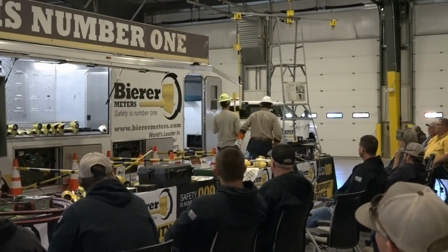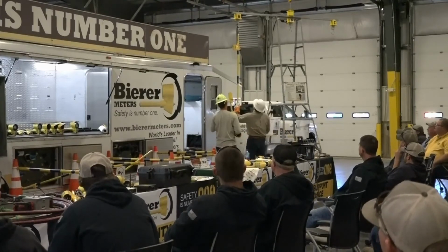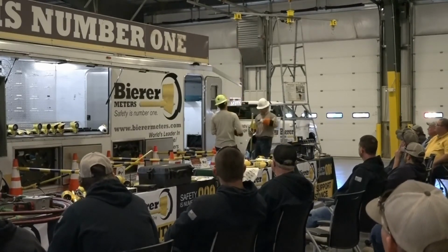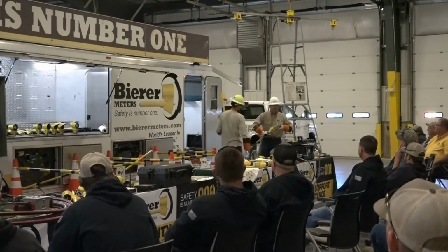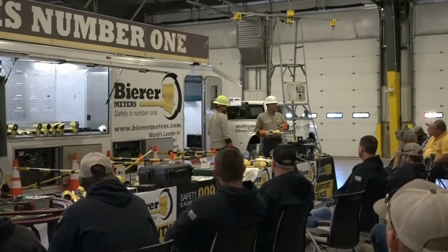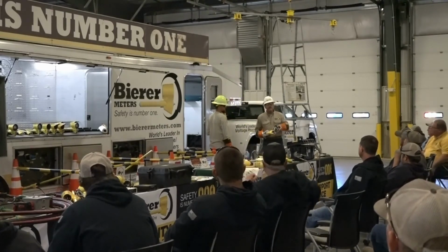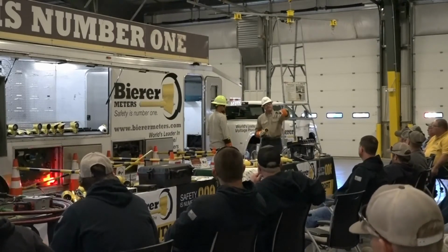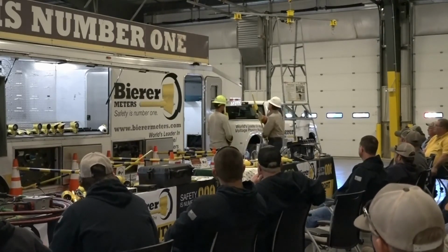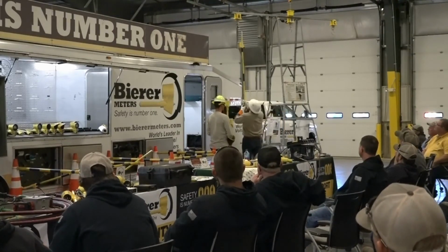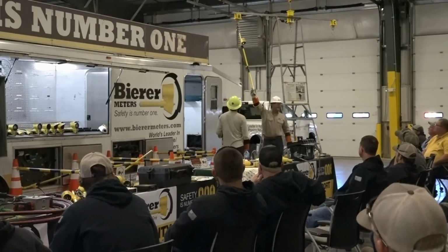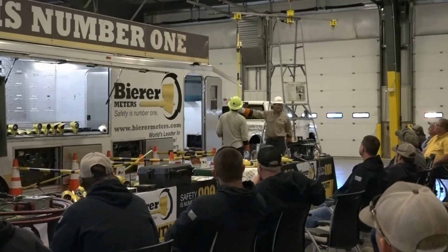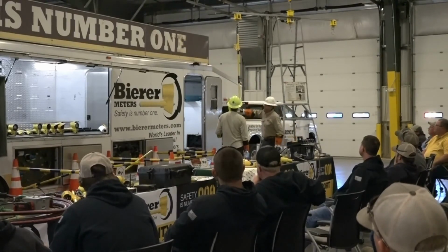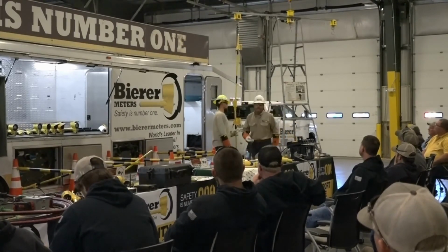You come this way. Okay, so I've got this reference probe, and I'm going to go to DEG, degrees. I'm not looking at overhead potential, I'm not looking at underground potential, I'm looking at the phase angle, so I go to degrees. And if it's energized, we'll see a white light. White light, we're energized. We already checked the battery, batteries are good.